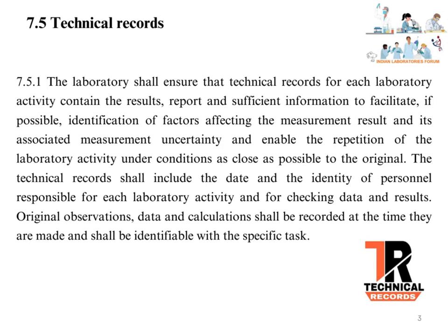The records should also enable the repetition of the laboratory activity under conditions as close as possible to the original. Each laboratory record should contain results, report, and sufficient information to establish the traceability of activities. Wherever possible, these technical records will be helpful in identifying factors affecting the measurement results and associated measurement uncertainty.